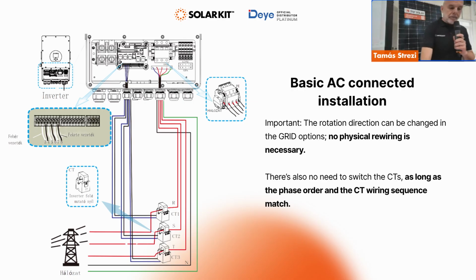systems of the house. As Peter has already mentioned, the rotation order of the phases is kind of a non-issue. It's not really important. You can change it anytime in the inverter settings. No physical connection changes are necessary. The only important thing is that your phases match the CT phases they're attached to exactly. You follow the same order and you are good.